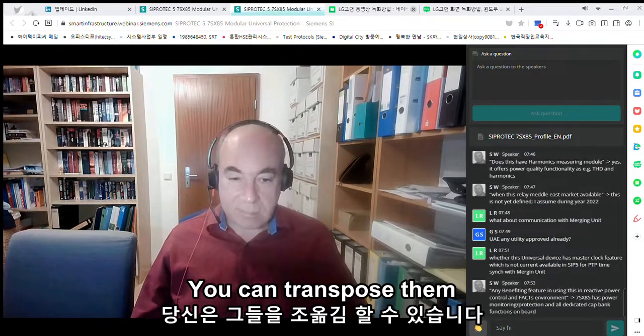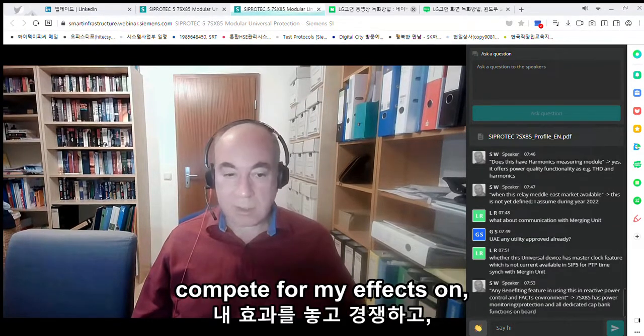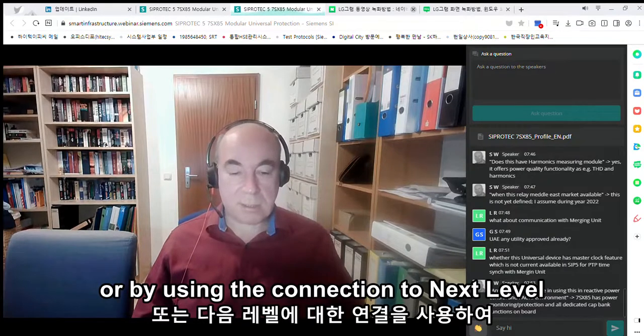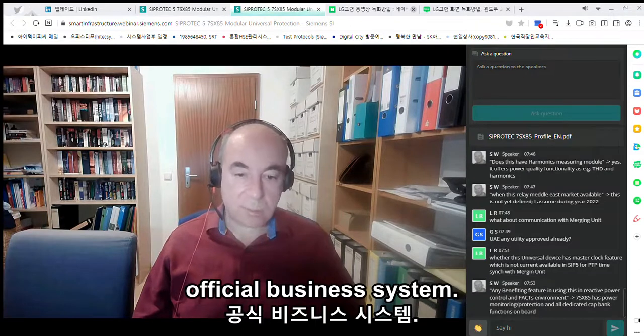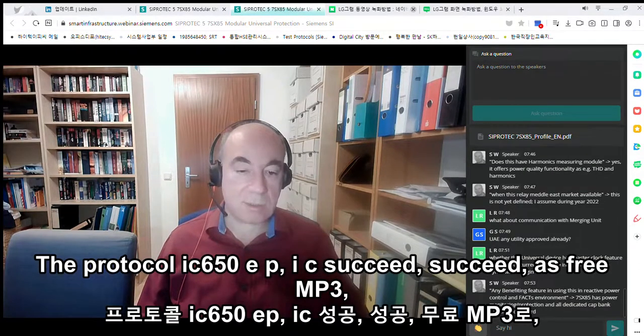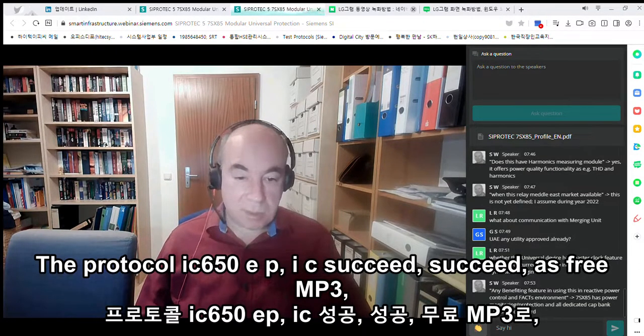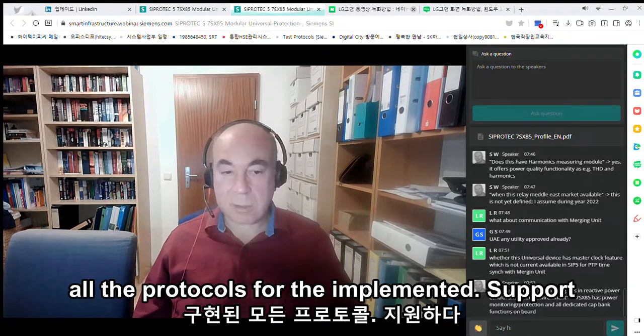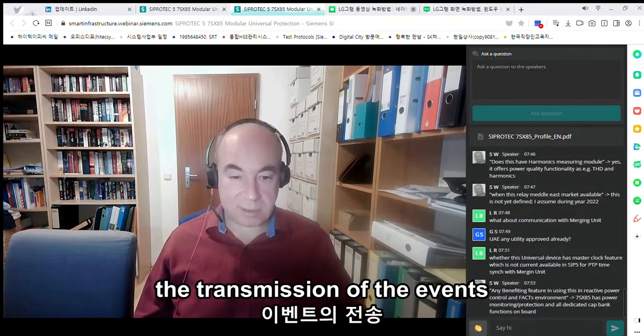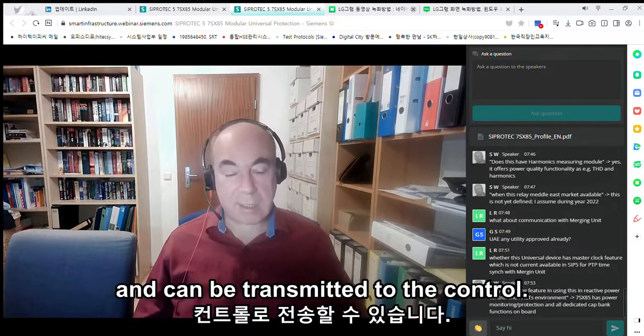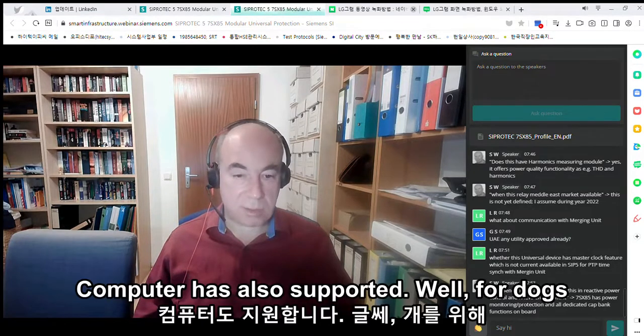You can transfer them via COMTRADE format, for example, or by using the connection to a next level substation automation system via protocols like IEC 61850, Modbus TCP, IEC 60870-5-103, DNP3. All the protocols implemented support the transmission of the events. They are stored in the device and can be transmitted via the communication module to a substation automation control system.